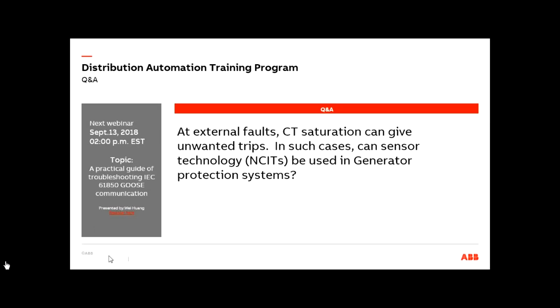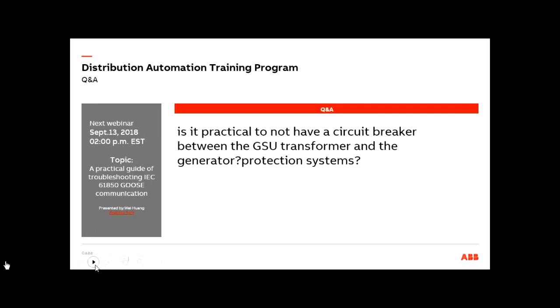It has just one big range for current measurement. The other benefit of a sensor is that it won't have saturation issues. So having an NCIT, a non-conventional instrument transformer, is the best method to go. But if we are applying it in an existing situation, then we may not have that. But sensor technology will help in avoiding CT saturation issues.